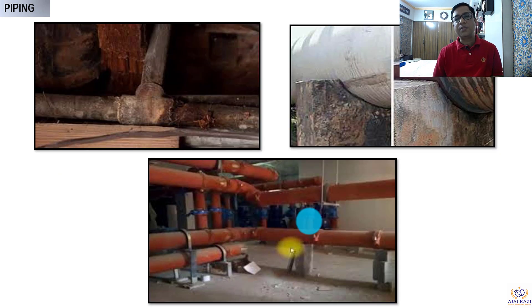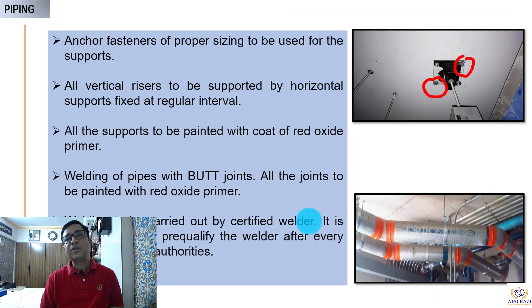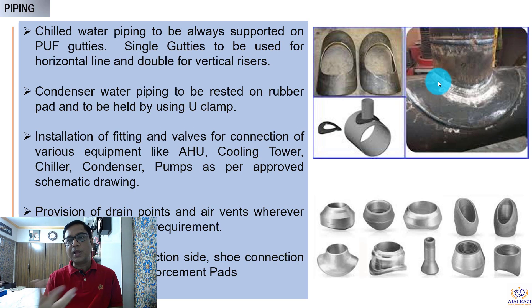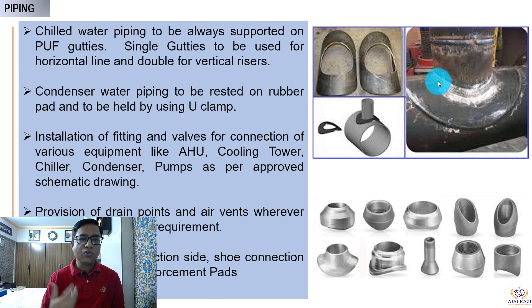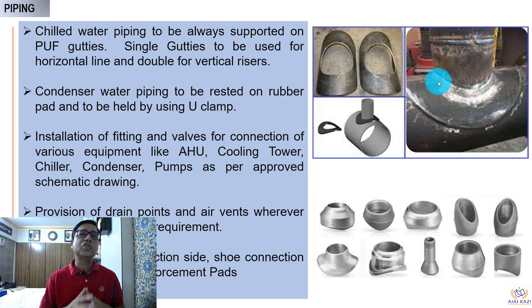Looking at some photographs, you can see bad installations for piping — it looks horrible, showing bad workmanship. Anchor fasteners play an important role; always ensure you have additional fasteners to handle any problems. If a fastener is designed to take the load and there is only one fastener, it is important to provide another so that if the first fails, the second takes care of it. Chilled water piping is supported on gutties — single gutties for horizontal and double gutties for vertical pipes. Clamps are used to hold pipes; for condenser water piping, normal clamps are used, but for chilled water piping, specifically designed clamps are used.